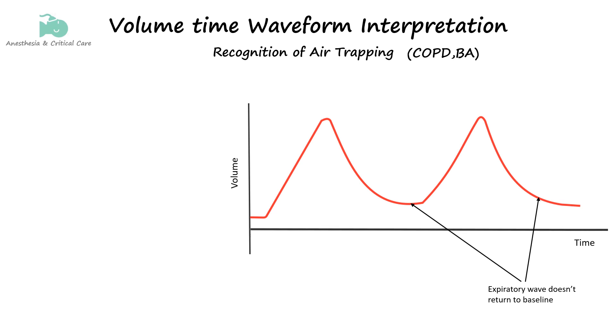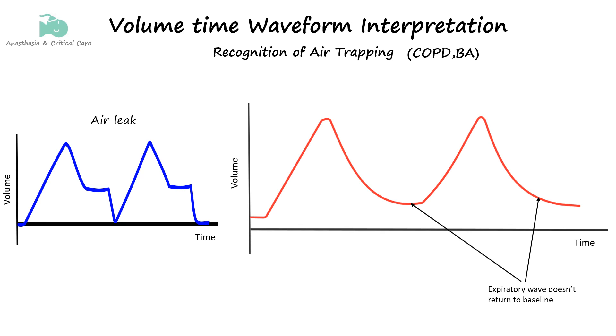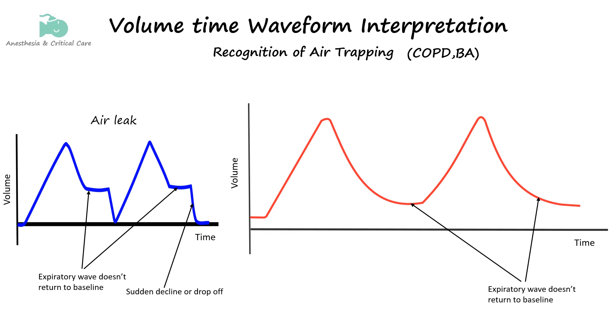Both air leak and air trapping cause the curve to not return to baseline, but for different reasons. In an air leak, the curve fails to return to baseline because air is escaping from the system, leading to a loss of volume — this can cause a rapid decline or sudden drop-off in the curve depending on the severity of the leak. In air trapping, the problem is incomplete exhalation, leading to residual air in the lungs; the curve flattens out as it approaches baseline but doesn't reach it. While both conditions result in a similar-looking waveform, the subtle differences in how the curve behaves can help differentiate between the two.